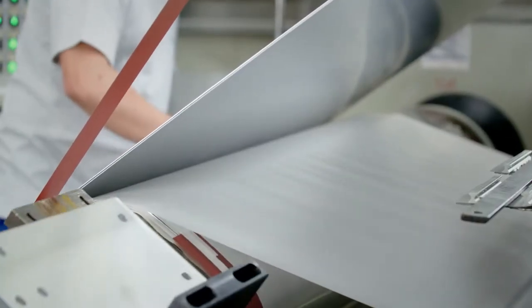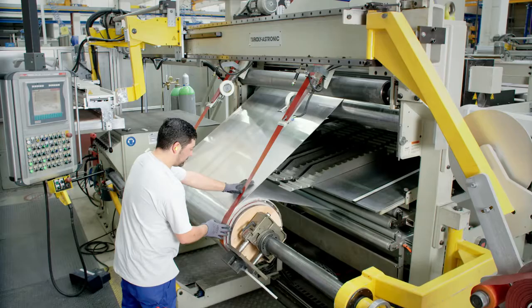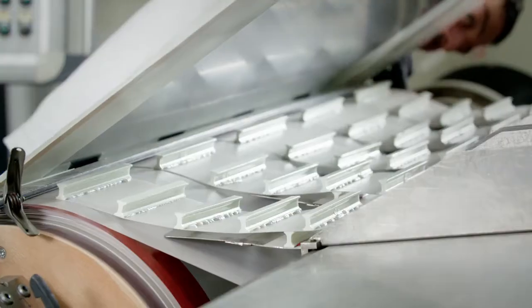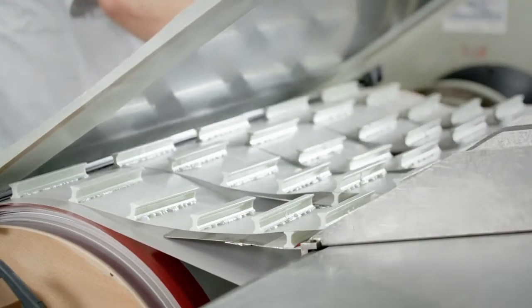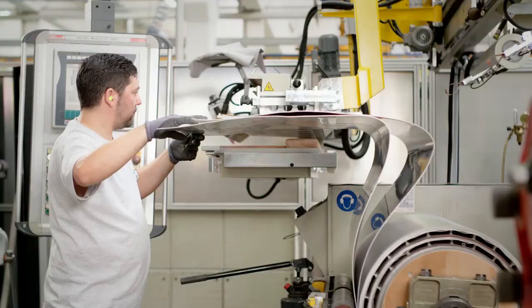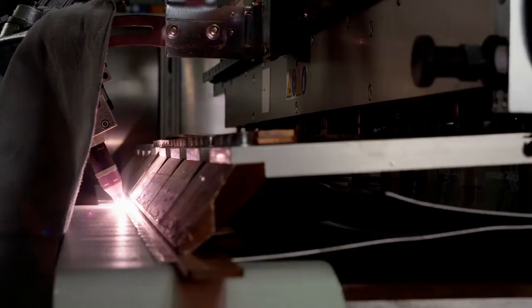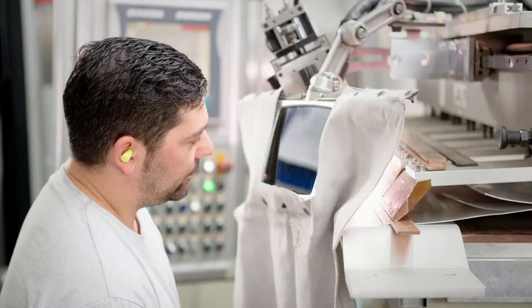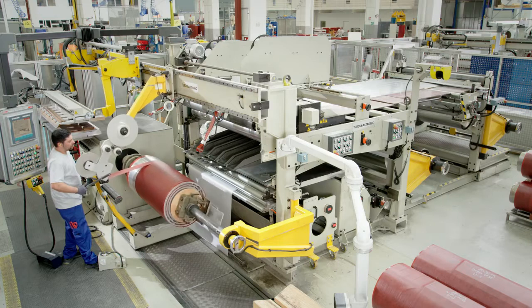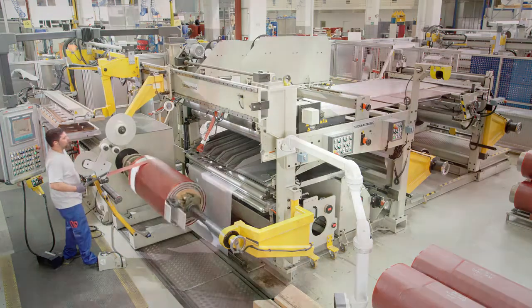A fiber-reinforced foil called pre-peg serves as a means of insulation. Spacers provide ventilation channels for better cooling. Consistently and highly precise, an automatic welder connects the coil with the low-voltage connections weld by weld. Thus, a light and highly robust coil is produced which can withstand mechanical stress just as well as it can withstand extreme cold or heat.